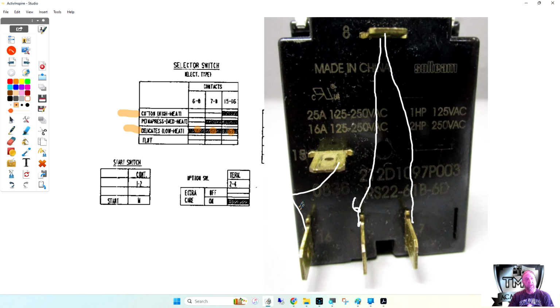So if I was to test this switch, I'd go to this chart. Depending on where the dial is set — just like we talked about the timer — you see here which ones are highlighted or shaded in, telling you if I chose this setting, these are the switches that are closed. This is how I'd check it: I check 6 and 8, put a meter lead on 8 and a meter lead on 6, and see if that switch is good. But the dial has to be in that setting.